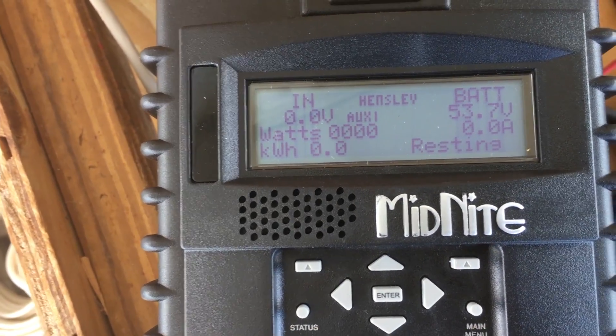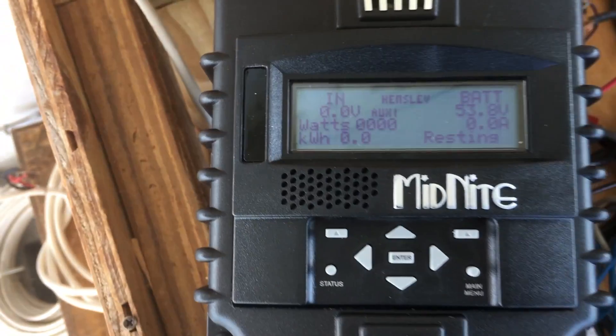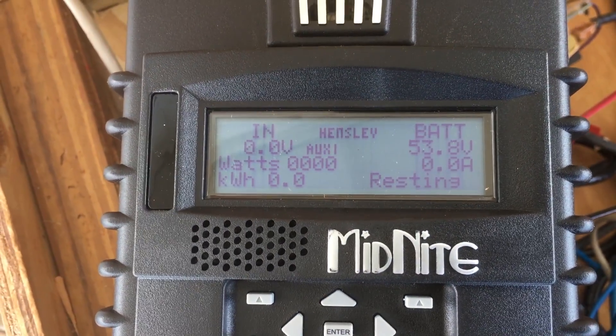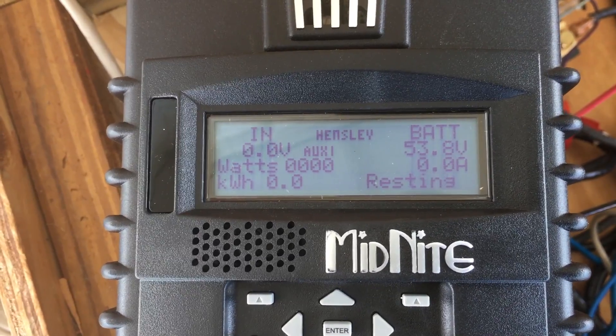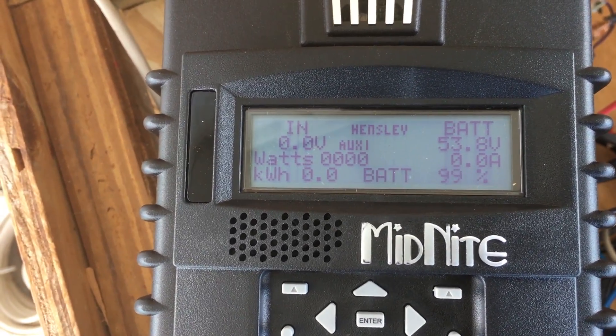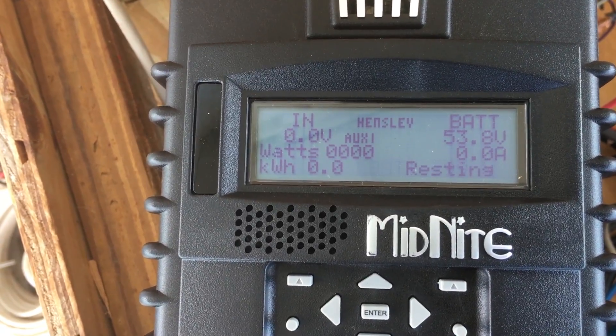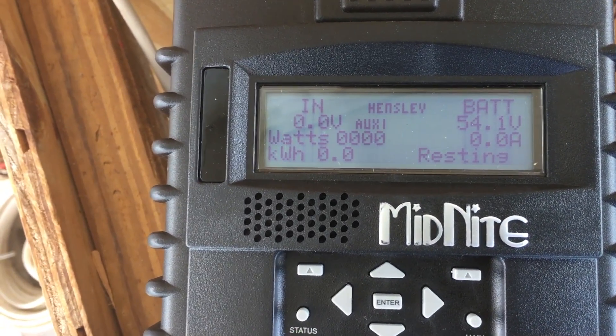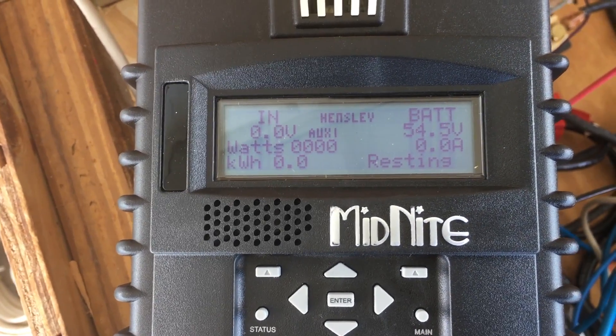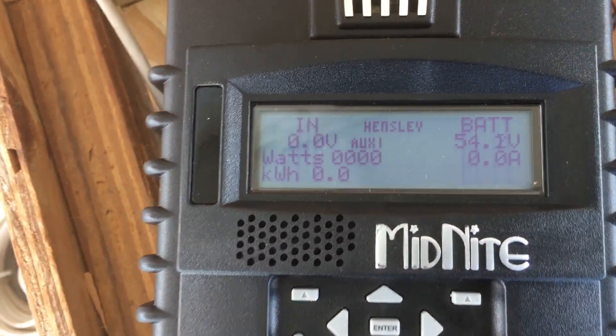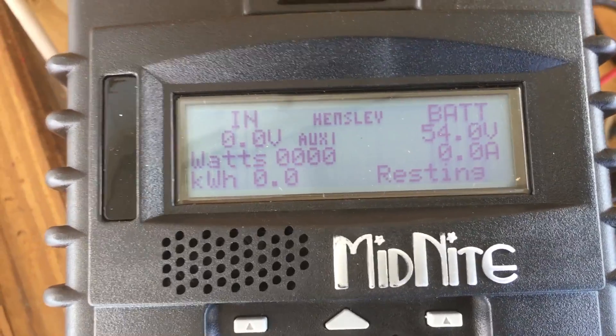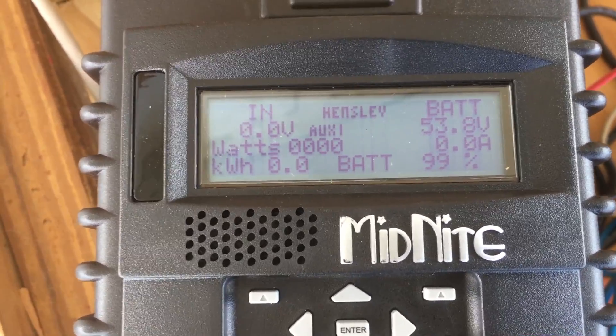And that is because the PV input voltage exceeds the ratings of over 250 volts. So that probably caused some damage inside. Other than that, the functionality is pretty much the same except the PV input.